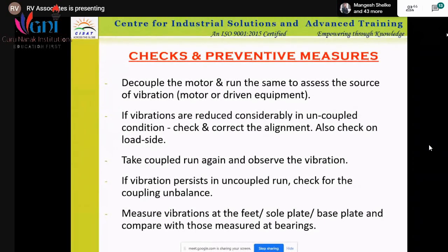Then if you know that there is some change or some vibration is more, you have to immediately stop the motor, decouple the motor, and start the motor again. Check whether there is a problem in the motor or a problem in the coupling. This is called the preventive measures.